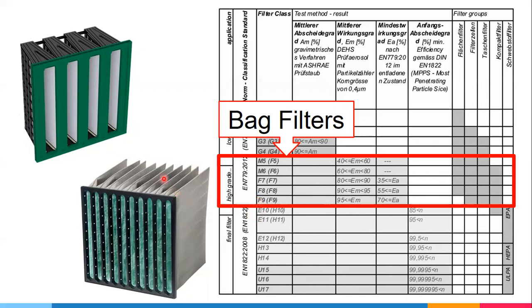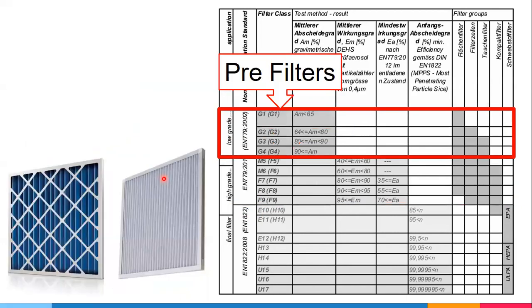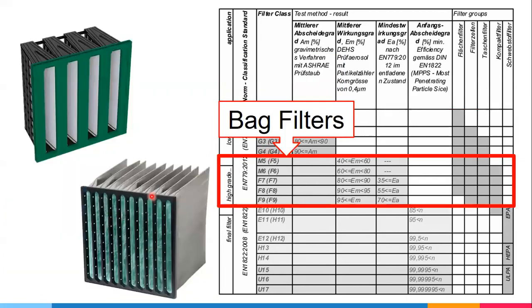Usually F9. So when you go to the AHU manufacturer, you would say you want your pre-filter to be G4 class, and your bag filters to be F9. You could also specify if you want the normal bag filter or the compact bag filter. The efficiency would be the same.